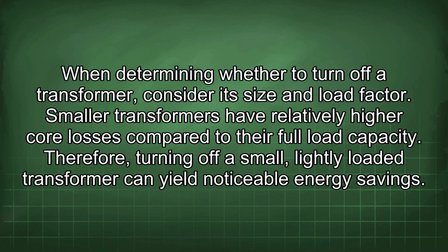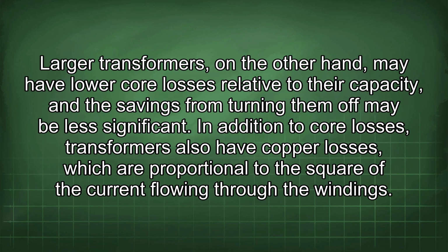When determining whether to turn off a transformer, consider its size and load factor. Smaller transformers have relatively higher core losses compared to their full load capacity. Therefore, turning off a small, lightly loaded transformer can yield noticeable energy savings. Larger transformers, on the other hand, may have lower core losses relative to their capacity, and the savings from turning them off may be less significant.